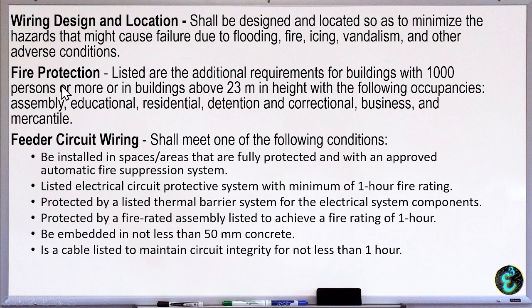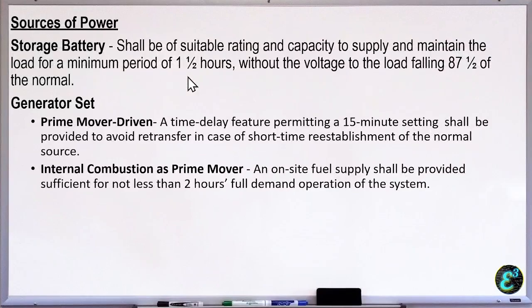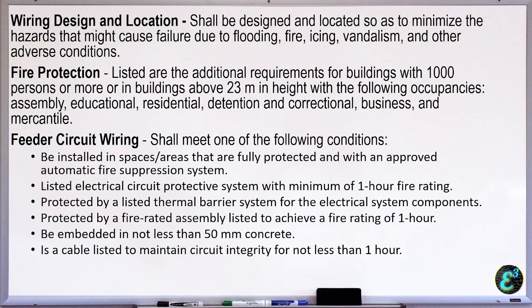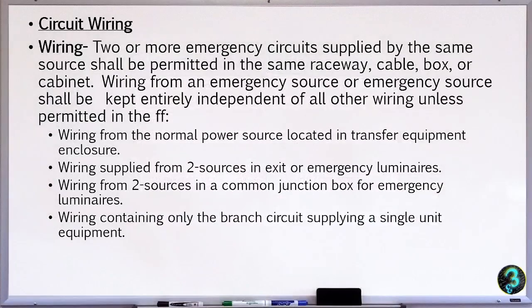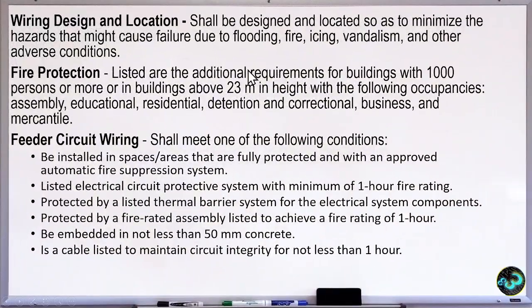Okay? So fire protection. Listed are the additional requirements for buildings with 1000 persons or more, and in buildings above 23 m in height, with the following occupancies: assembly, educational, residential, detention and correctional, including business and mercantile or merchandise. Now, feeder circuit wiring shall meet the following for emergency system.